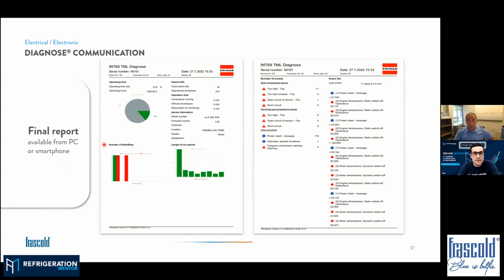It gives a number of interesting informations, like for example the last 20 events or the last 7 days of alarms. It gives you the number of starts and stops, how many starts in 1 hour the compressor has tried to ramp up, and all this kind of information. Of course, also about trips on the PTCs and oil pumps as well. So it gives you already an idea.